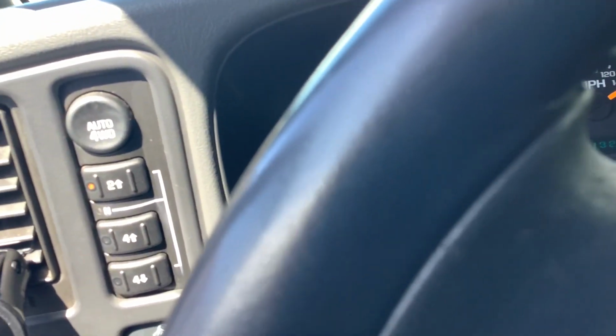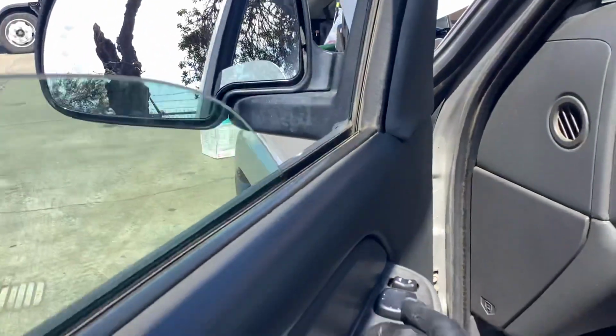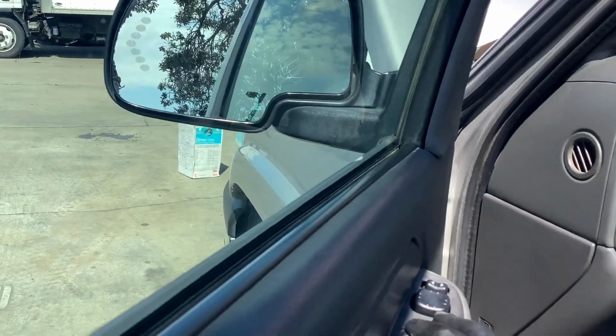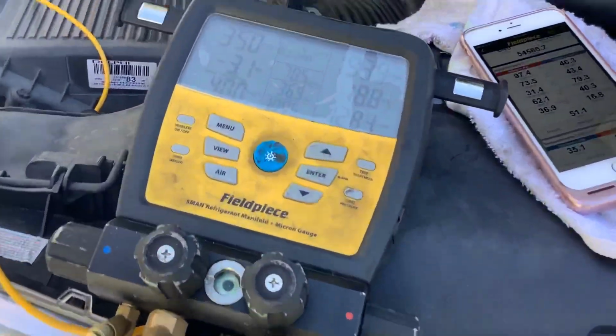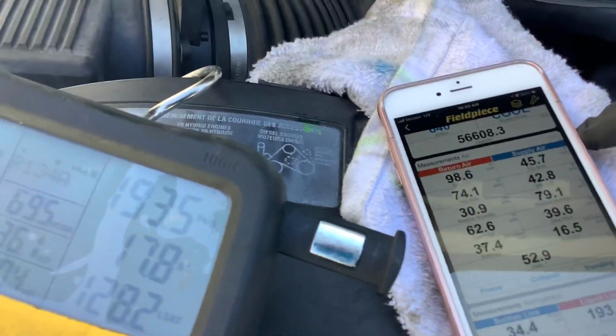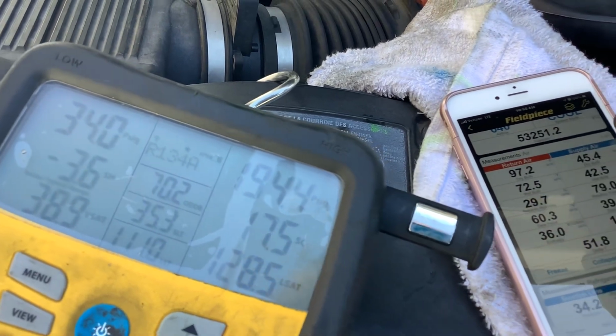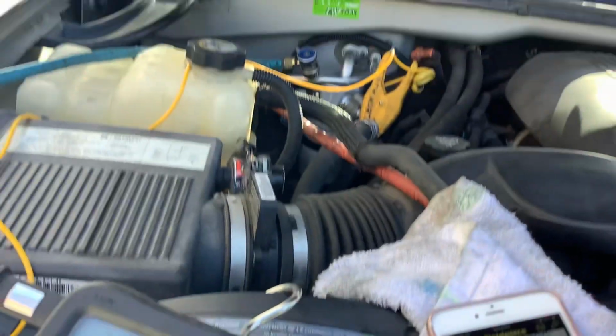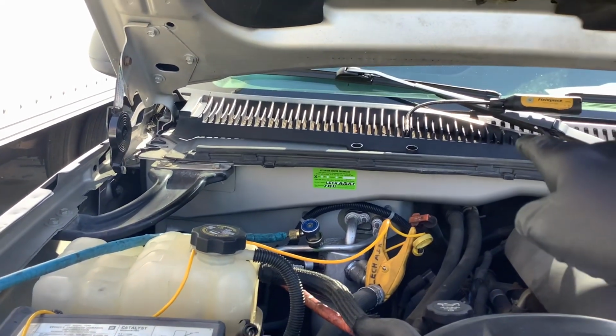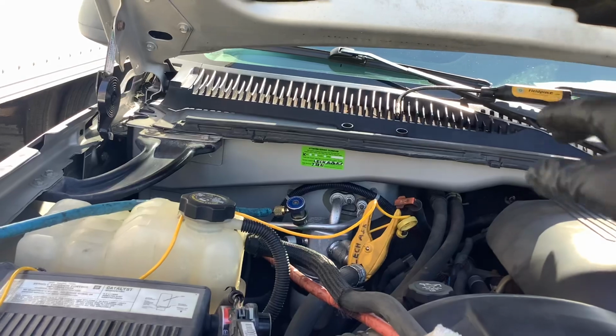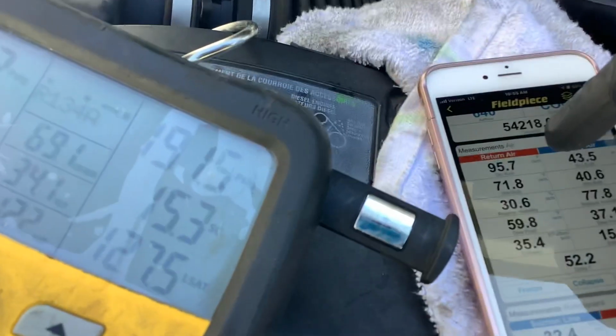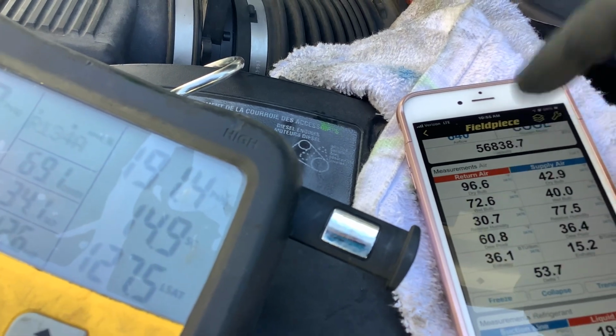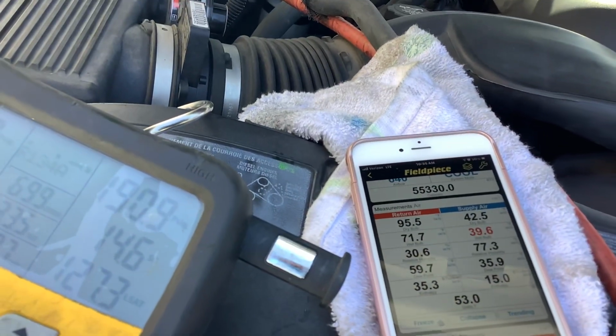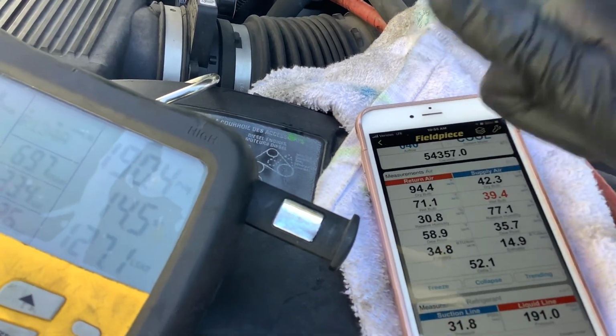So we're hanging right around 1600 RPMs. I will put this window up, and we'll close this window gently and this door so I don't knock my high-tech, high-dollar pedal depressor off. And this will take a few minutes, but we'll start to see it come down. So you already can see our interior supplies down to 45 degrees. And you see 97, 96 degrees because we're no longer sucking air. We don't have a negative pressure sucking this hot air in. So more of the cold ambient temperature is flowing over that probe up there. And that's why we dropped from 100 or 114 degrees down to 95, because there's no airflow. If I turn it back on to fresh air mode, you would see this hot temperature go up.